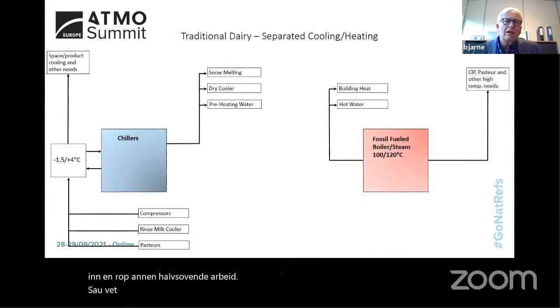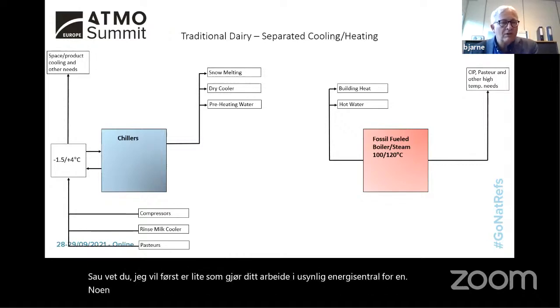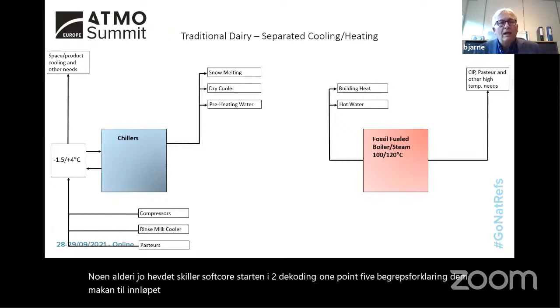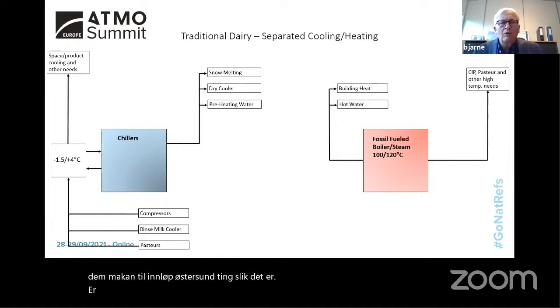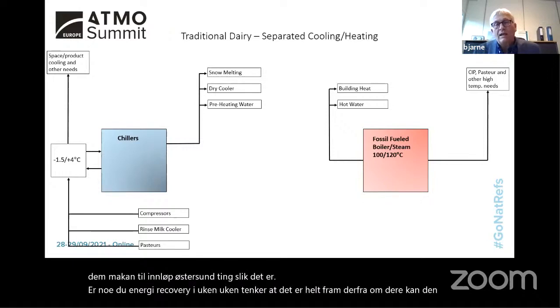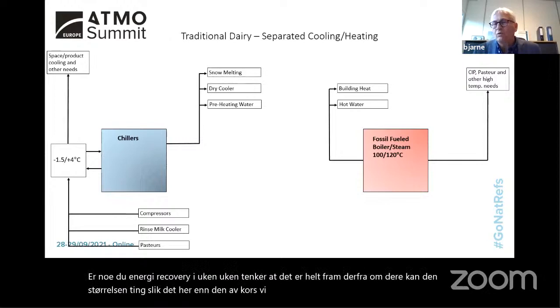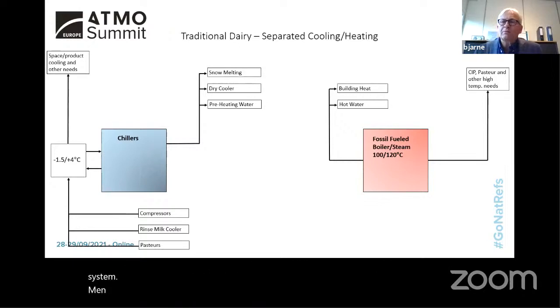I would like to show you a detail of the usual energy central for a normal dairy. You have the chillers, of course, that you need for cooling, 1.5 degrees for cooling the milk and cooling all the pasteurs and things like that. When you do energy recovery, you can take out the heat from the condensers and things like that. Then, of course, you have a boiler, like a fossil fuel boiler - that's the standard system. Then you can heat the pasteurs and things, and of course also heat buildings and hot water and everything from that.